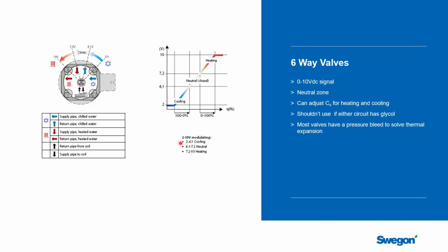I'm saying that backwards actually. We're going to go from high flow to low flow. Then we're going to reach the neutral, where neither circuit is open to the coil, so that you're in the dead band. And then if the voltage gets between, say, 7.2 and 10 volts, you're going to start to modulate the heat on. And so the unit controller, the zone controller, just sends one 0 to 10 volt signal out to this valve, and then it will modulate the two different loops.